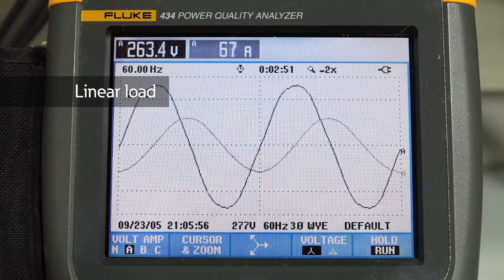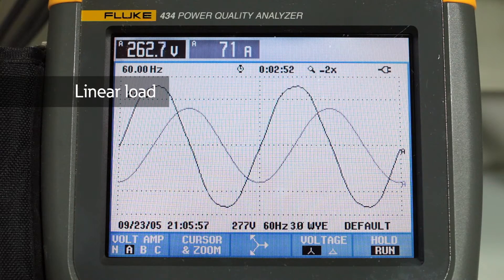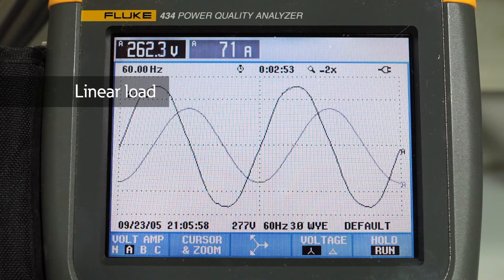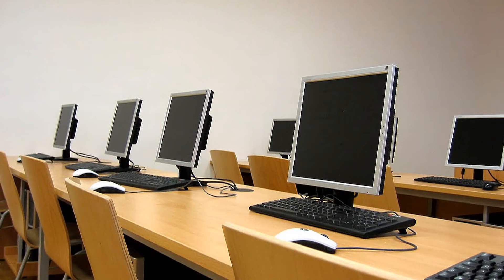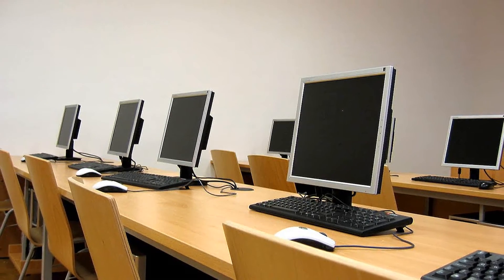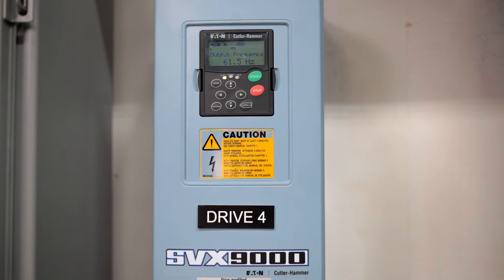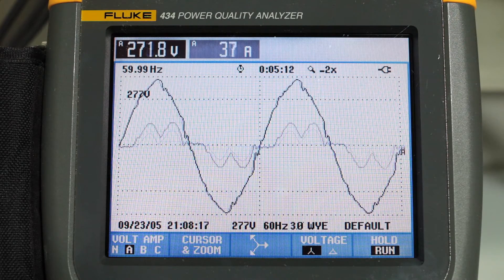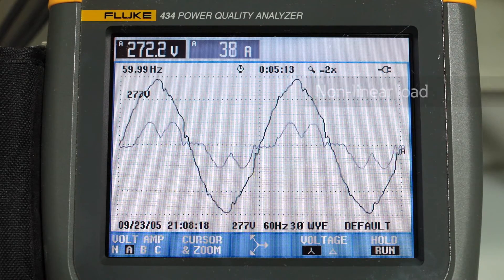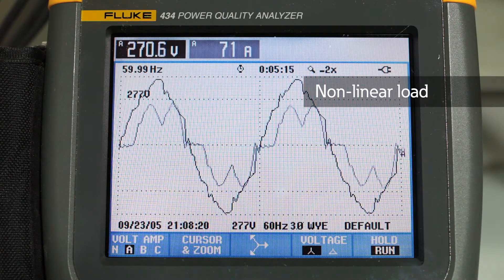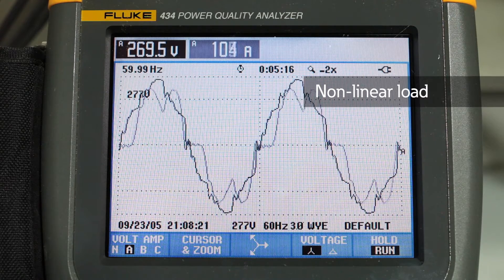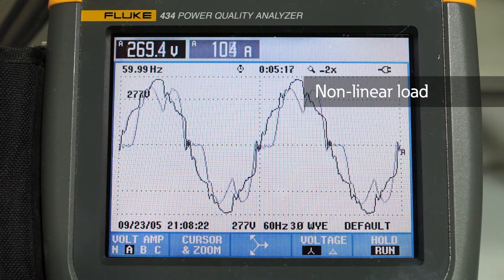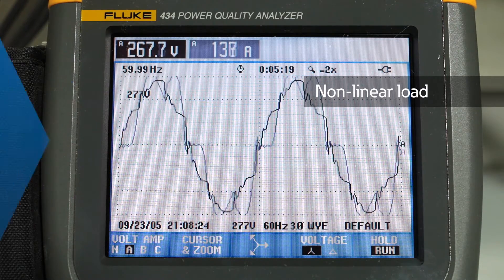We call these loads linear because the current they draw looks similar to the voltage. Non-linear loads such as computers with switch mode power supplies, fluorescent lights, and variable frequency drives draw current that does not look similar to the voltage. This non-60 Hz current distorts the waveforms of the entire distribution system.